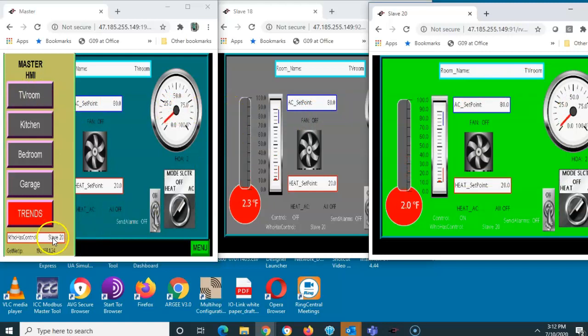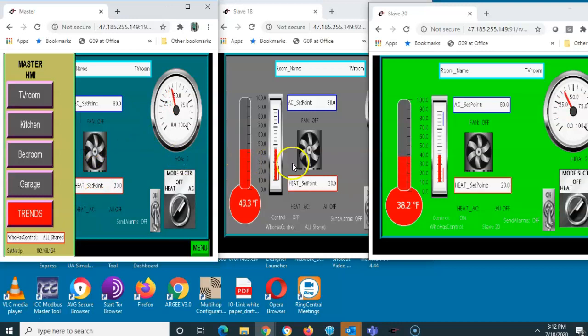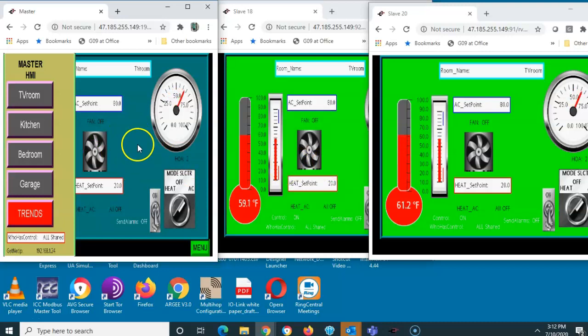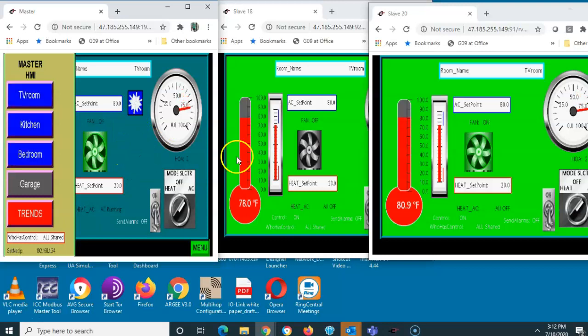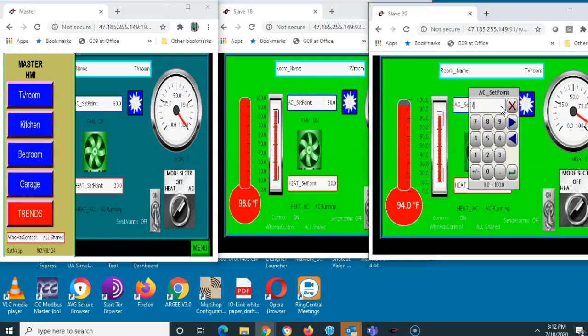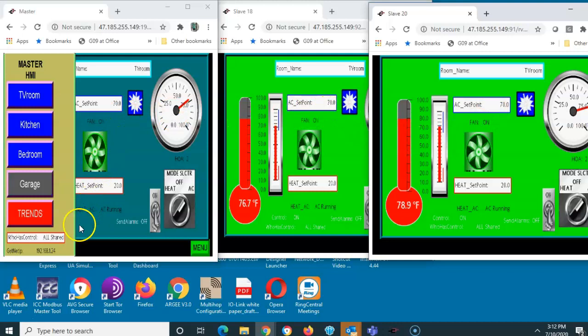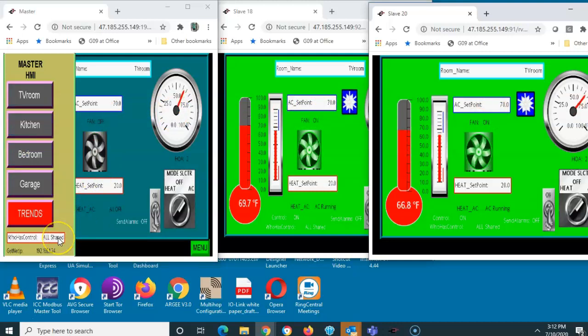If I want all screens to have control, I can hit the pull-down and select 'all shared.' Now both slave HMIs will show green, indicating either one can make changes. The master background doesn't change because it's always in control. So if I change the setpoint to 70, it changes throughout all displays.